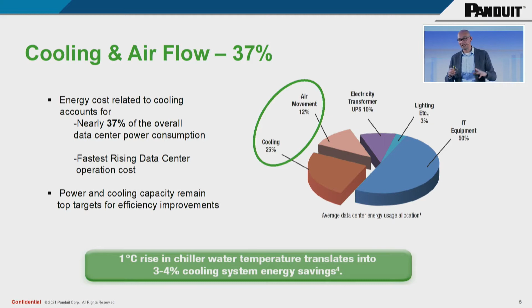We've come up with this acronym: if you're able to control the hot aisle, cold aisle separation at around 0 to 8 kilowatts, that works really well. As you go north of 8 kilowatts, you start looking at controlling the airflow with a cold aisle and hot aisle. When you go north of that, at 40, 50 kilowatts, you're probably looking at hot air containment.